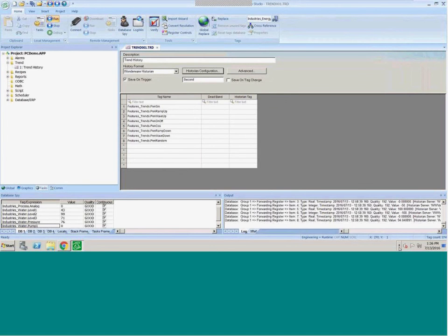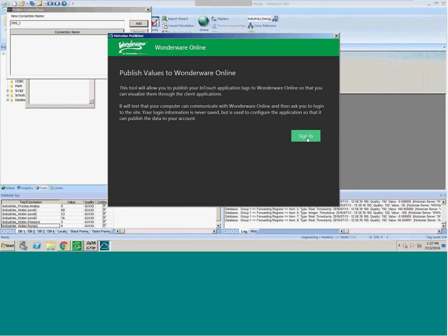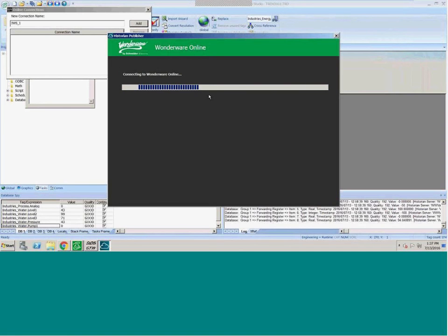If I look at the Wonderware Historian in the configuration, I have an on-premises connection — this is my server machine name and login information, so I'm going to a local historian. If I want to go to Wonderware Online, I first have to create a connection through the gateway itself. So if I open up Studio Database Gateway and create a new Wonderware Online connection — I'll call this IWS_one — the first thing it's going to do is prompt me to sign in to Wonderware Online and establish a connection against the Microsoft Azure Active Directory. In the onboarding of different users to Wonderware Online, the administrator can invite additional people to a particular tenancy because Wonderware Online is a multi-tenant solution.